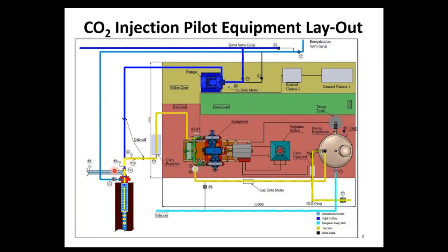Of course, you can use pressure, but it's going to be high pressure, high temperature, and the efficiency is going to come down. Our purpose is decreasing the cost of CO2 reinjection, and that is why we designed this special ejector, to make it cost efficient. At the same time, as you see, there is a brine reinjection system. The brine goes down, the gas goes down at the wellhead, and it continues to go down, since this motivating fluid vacuums and moves down in the smaller string.